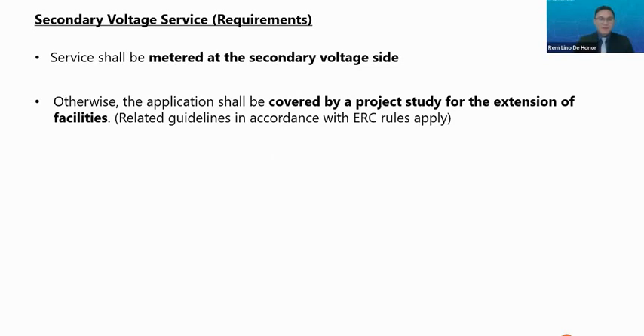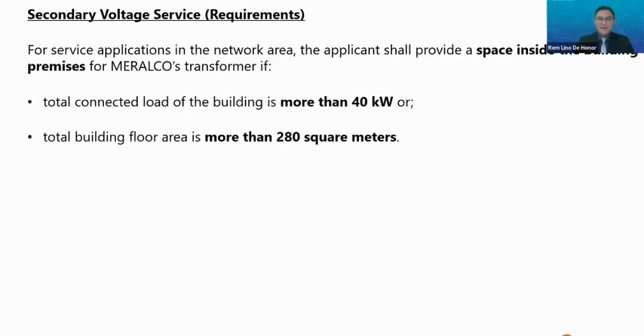Secondary voltage service requirements. First, it shall be metered at the secondary voltage side. Otherwise, if there are no available facilities, the application shall be subject to a project study for the extension of facilities. The applicant shall provide a space inside the building premises for the Meralco transformer if, first, the total connected load is more than 40 kilowatts, and second, the total building floor area is more than 280 square meters.